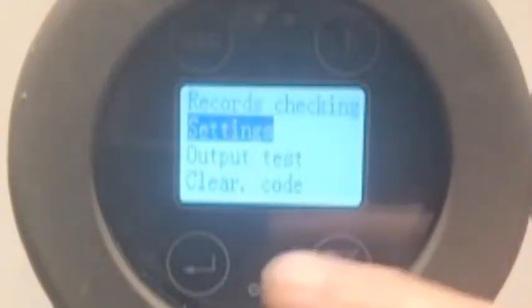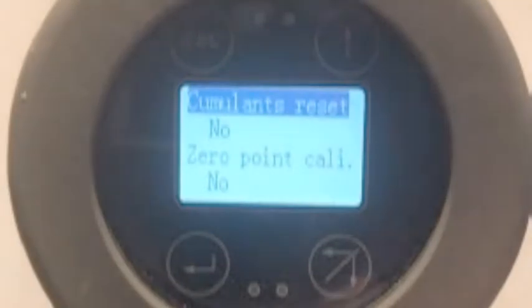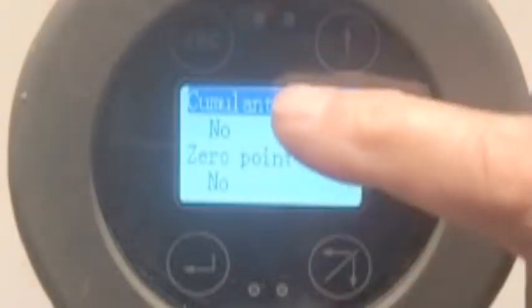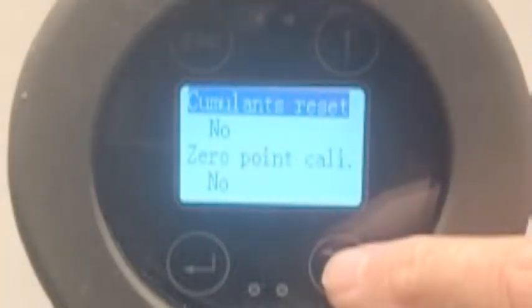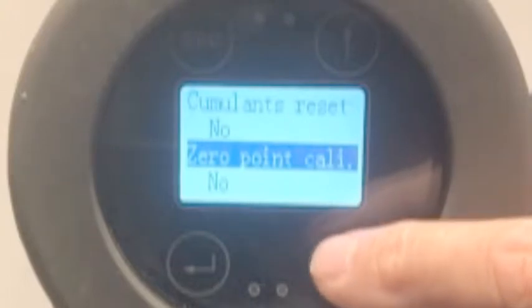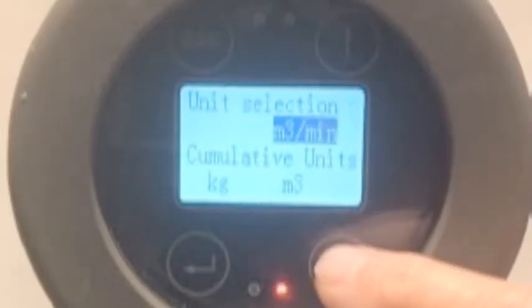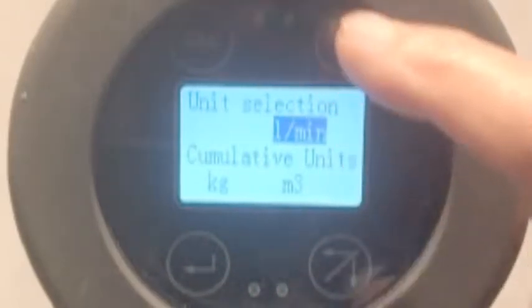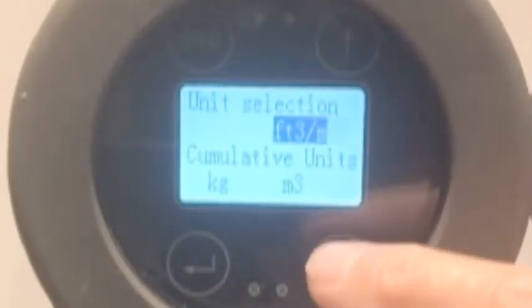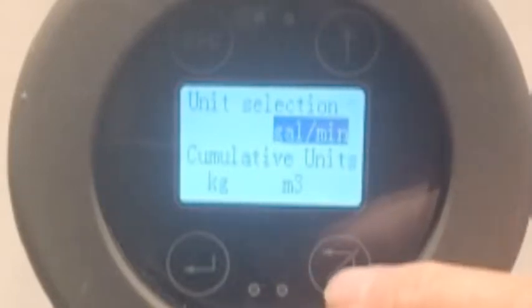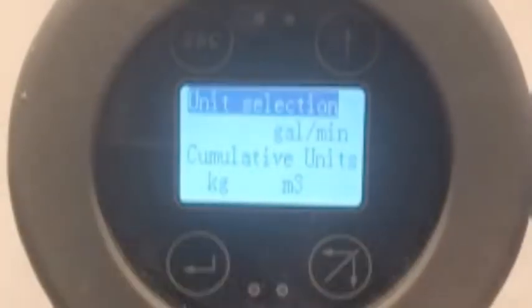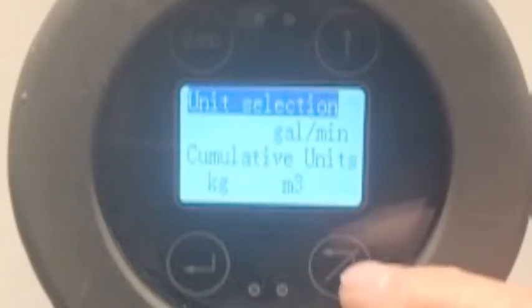I'm going to go down to Settings and hit Enter. I can look and see whether I want to set the totalizers — cumulative totalizers — or do a zero point calibration. I can select the units. Let's select the units and change them to something different. I hit Enter, cycle through, and let's set it to gallons per minute. Click Enter. Now the unit selection is gallons per minute.